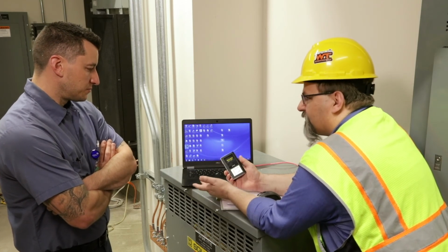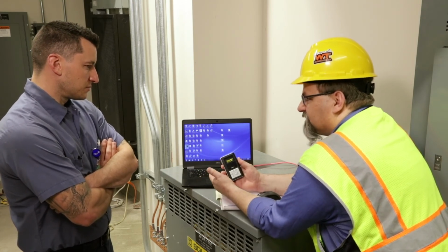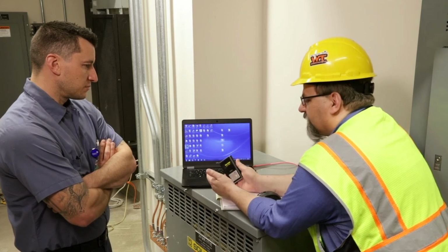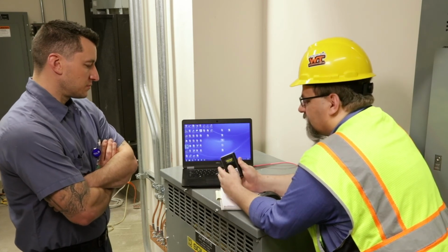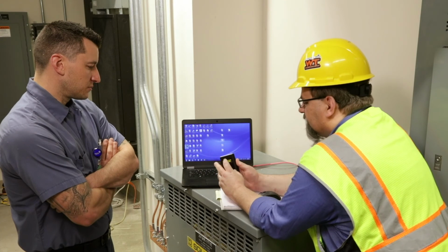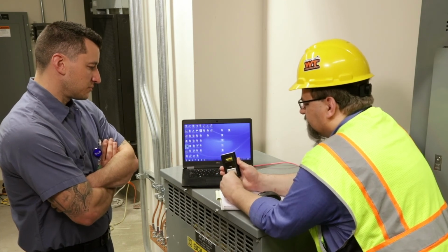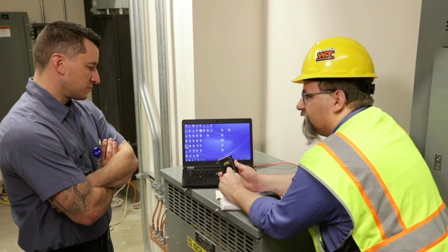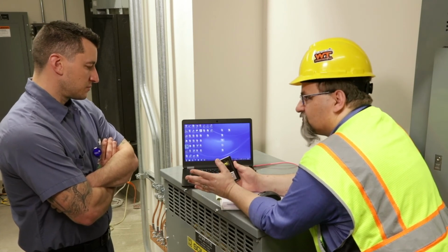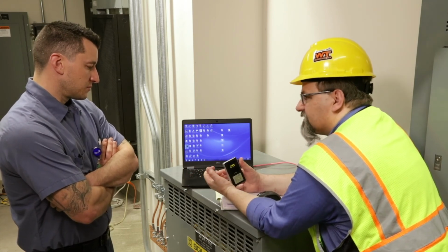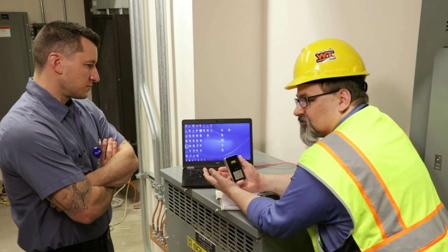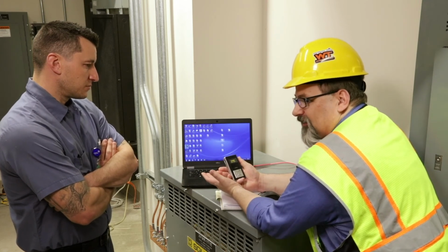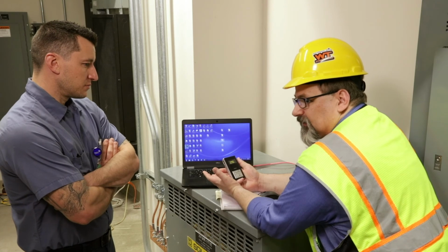In a really bright room, if you're on the first floor and the sensor's up on the second floor, it can be really difficult. But if you hold it still and you aim at a sensor and you press that button, it pulls down the sensor's information. As soon as it does, you know A, that the sensor has power, and B, that the sensor is connected to something that's giving it power and is making sense of it, right?